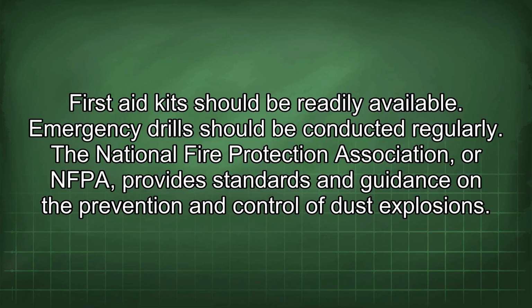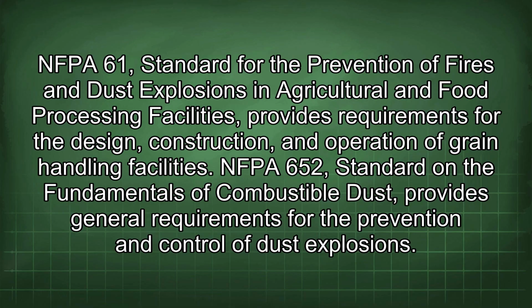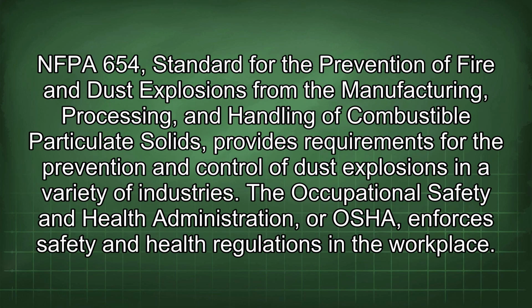The National Fire Protection Association, or NFPA, provides standards and guidance on the prevention and control of dust explosions. NFPA 61, Standard for the Prevention of Fires and Dust Explosions in Agricultural and Food Processing Facilities, provides requirements for the design, construction, and operation of grain handling facilities. NFPA 652, Standard on the Fundamentals of Combustible Dust, provides general requirements for the prevention and control of dust explosions. NFPA 654, Standard for the Prevention of Fire and Dust Explosions from the Manufacturing, Processing, and Handling of Combustible Particulate Solids, provides requirements for the prevention and control of dust explosions in a variety of industries.